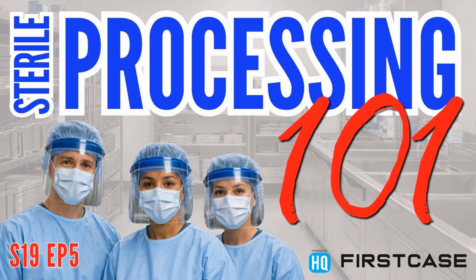Yeah. And what kind of instruments are we talking about? What are some examples of those? Yep. So primarily going to be flexible scopes, like if you use a flexible ureteroscope or something in the operating room that needs to be sterile, that's going to go through one of these sterilizers. And then other things that are delicate that can't handle the high temp, high steam, or high pressure of the steam. Things like maybe your orthopedic batteries or some of your other scopes or power equipment.